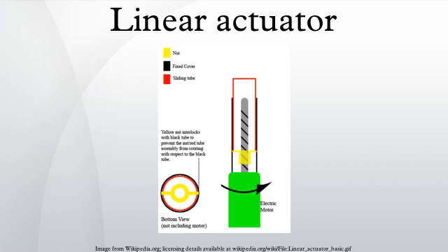Speed control. In most cases when using an electromechanical actuator, it is preferred to have some type of speed control. Such controllers vary the voltage supplied to the motor, which in turn changes the speed at which the lead screw turns. Duty cycle. The duty cycle of a motor refers to the amount of time the actuator can be run before it needs to cool down. Staying within this guideline when operating an actuator is key to its longevity and performance. If the duty cycle rating is exceeded, then overheating, loss of power, and eventual burning of the motor is risked.